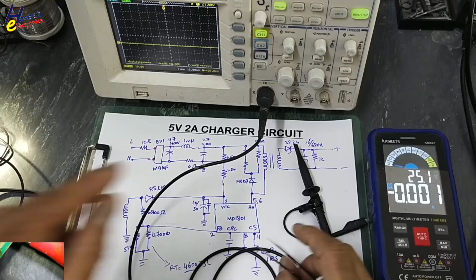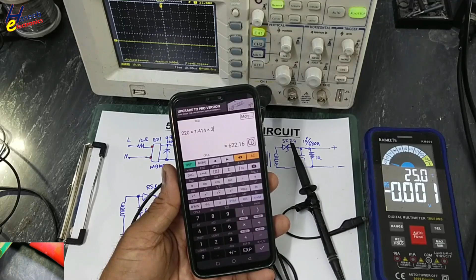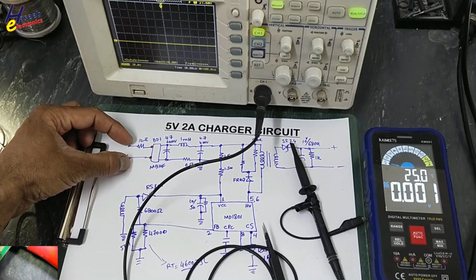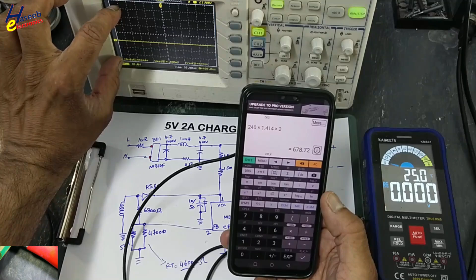If I want to test 220 volt line voltage, 220 multiplied by 1.414 gives peak voltage of 311 volts, multiplied by 2 gives 622 volt peak to peak voltage present in the line voltage. So if you test line voltage directly here, that will be 622 volts; in case the voltage is 240 volts, it becomes 678 volts. That is also within limit, so we can test line voltage here.